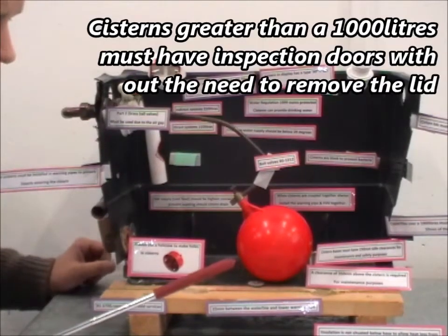Above the cistern should be 350mm clearance for maintenance purposes. So you could bend in, lean in, and have a look and inspect the cistern, maybe change the ball valve.